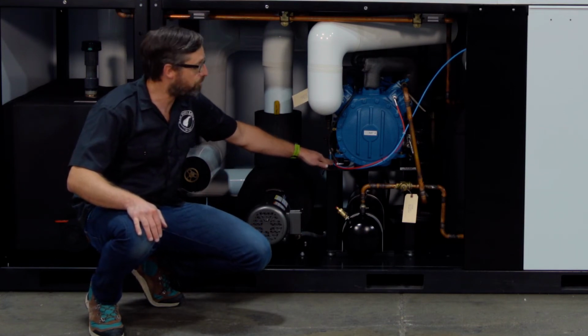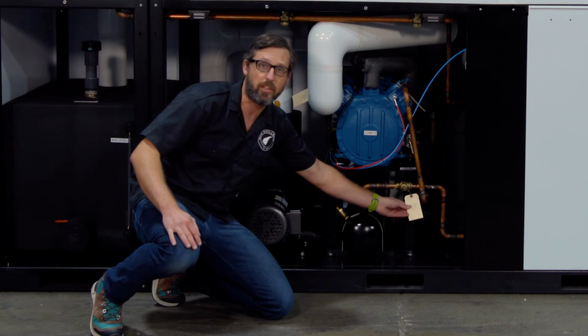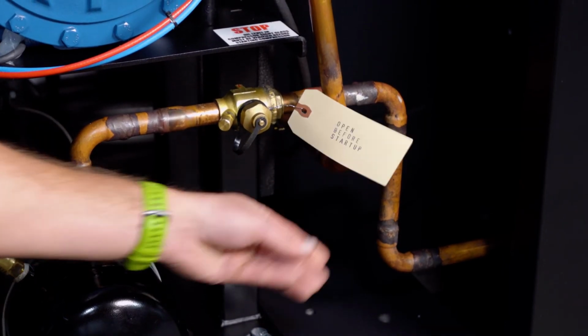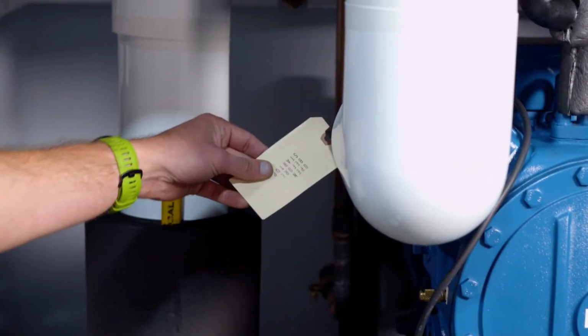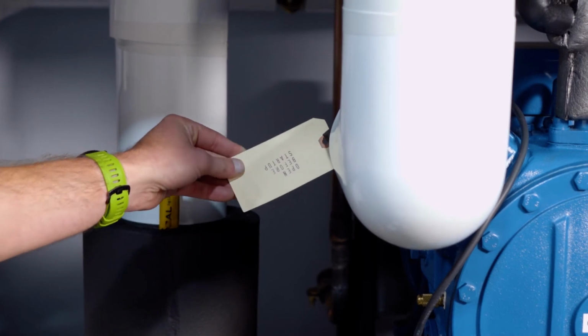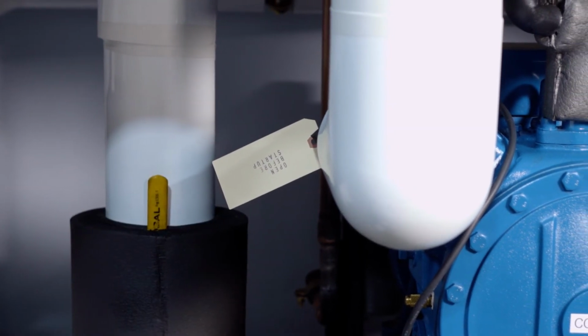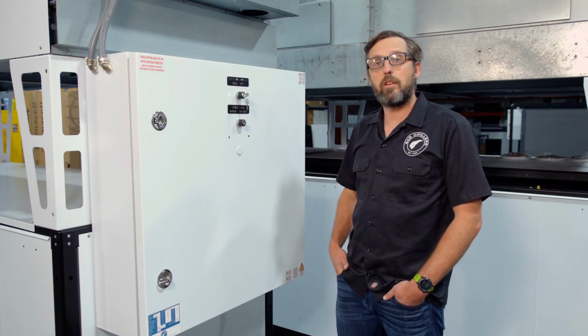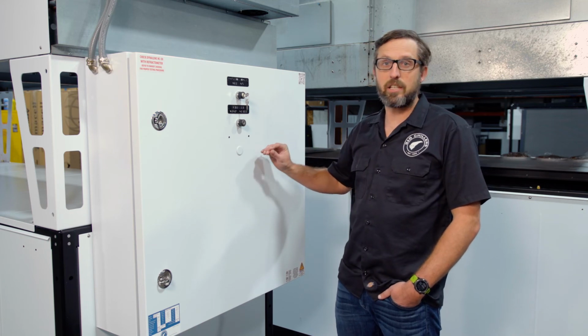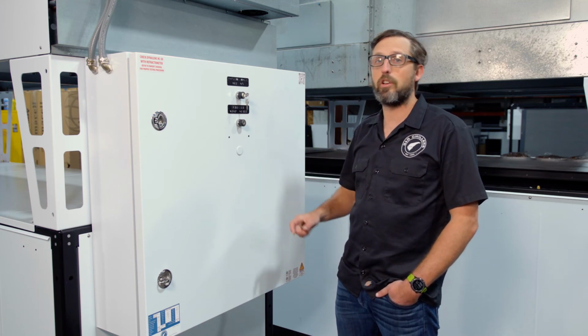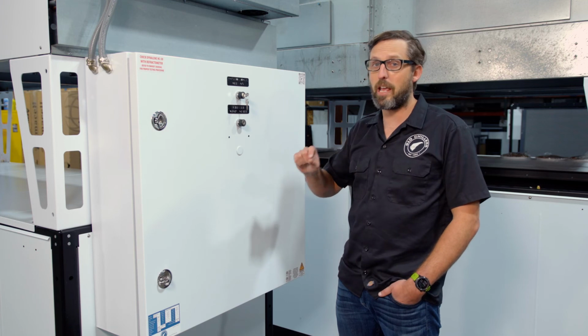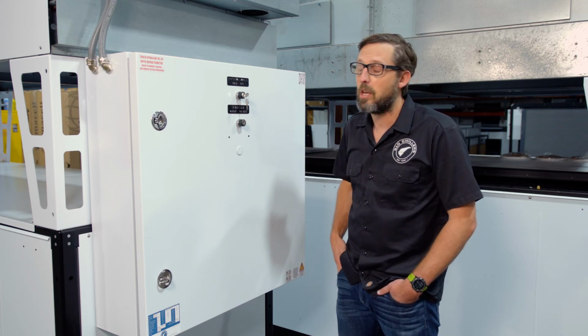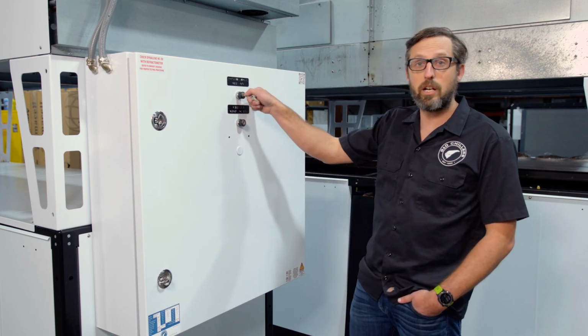Once you've ensured that, you're going to come through to each one of these service valves. In each unit there's a different number, so just be certain that you double check and make sure that all of the tagged valves, each one will be tagged, you open. Alright, so we've ensured that there is an oil level in the sight glass for each compressor in the unit. We've also been sure to double check and open every single tagged service valve. Once we've done that, we'll come back over here to the control panel.